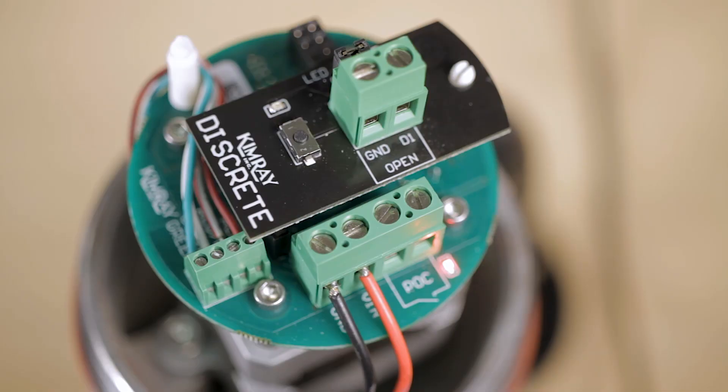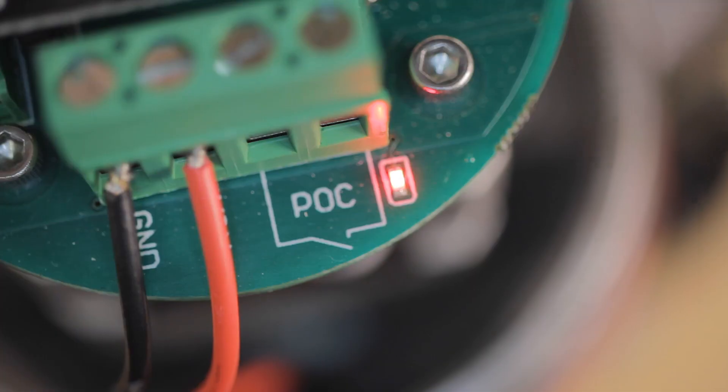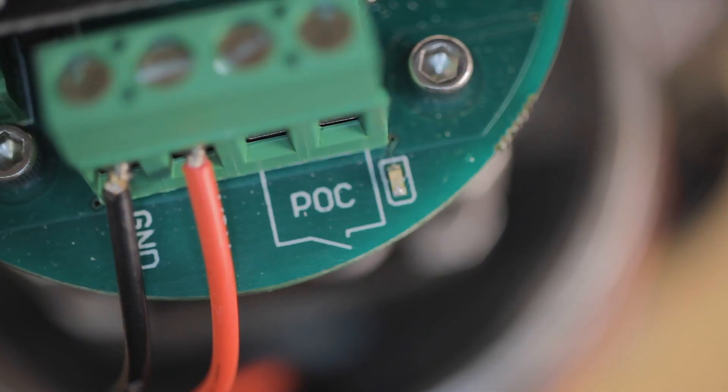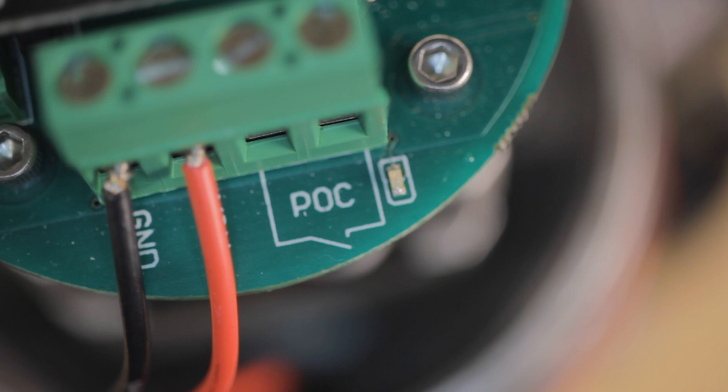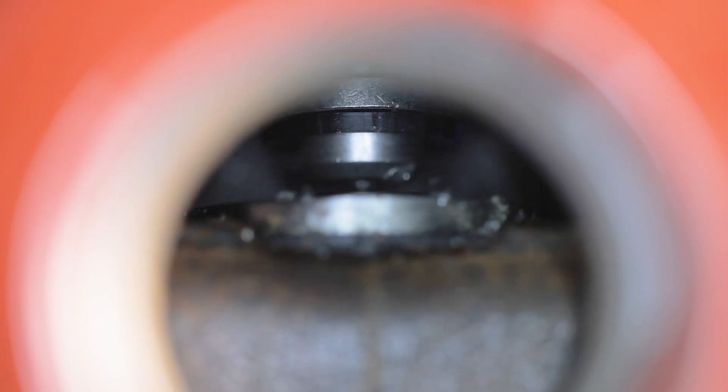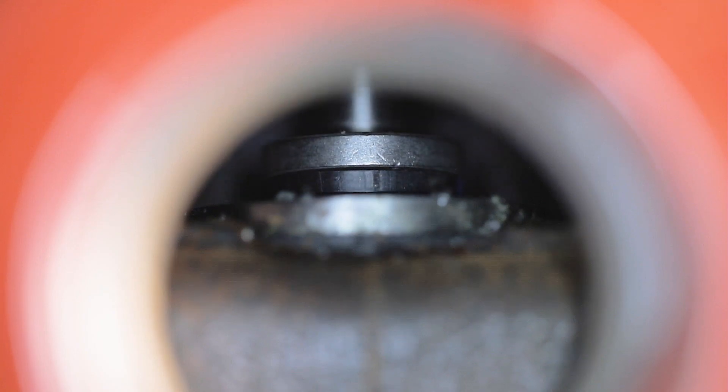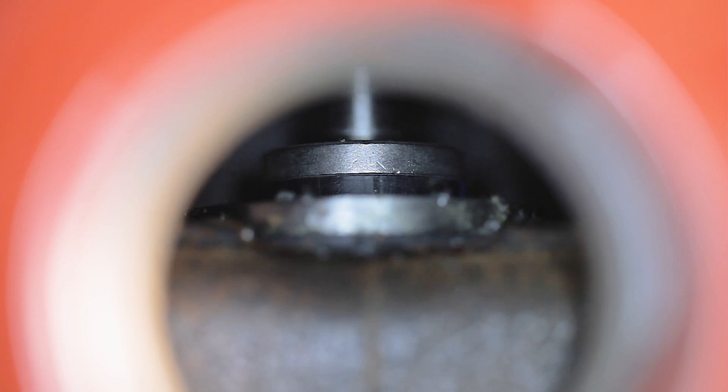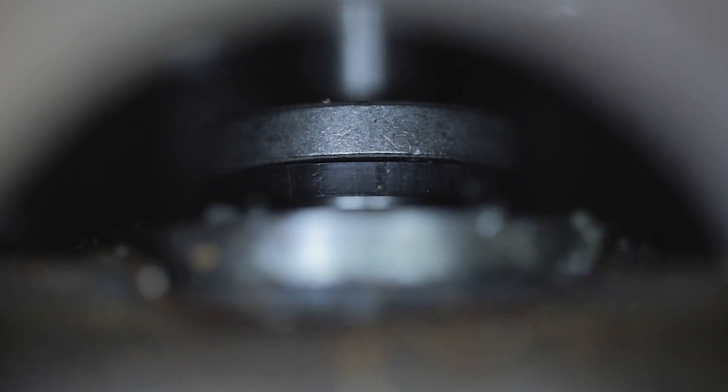There's a 4-pin connector with the voltage in and ground on the board itself, and there's a proof of closure connection for discrete output to an LED or an auxiliary alarm to let you know that it's seated. On initial power-up, the motor will drive the seat completely closed and you'll get an LED indication.